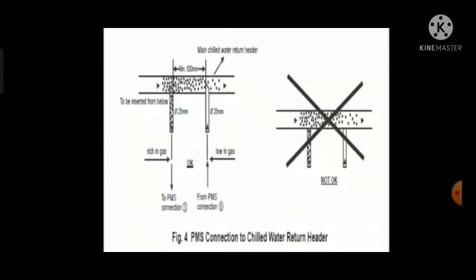Because the air is dissolved inside the water flowing in the chilled water circuit, and the air velocity is highest at the central axis of this pipeline. So the dissolved air is mostly found at the central axis of the chilled water pipeline. So we have to insert this pipe up to almost the central axis, because this unit will work as an air separator also. The main function of this unit is to separate air while maintaining pressure. So this pipe must be taken care of while installing, and it should be installed exactly as shown in this diagram.